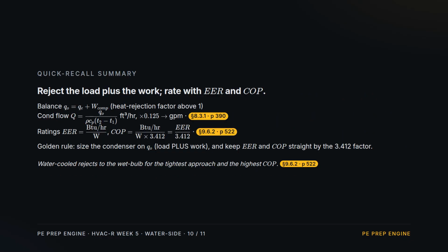Quick recall. Condenser heat rejection is the evaporator load plus the compressor work. So the heat rejection factor sits above 1. Condensing water flow is that rejection over the water's volumetric heat capacity times the temperature rise, in cubic feet per hour, times 0.125 for GPM. EER is BTU per hour per watt. COP is the same capacity over watts times 3.412, which is EER over that factor. Golden rule, size the condenser on load plus work and keep the two ratings straight by 3.412.